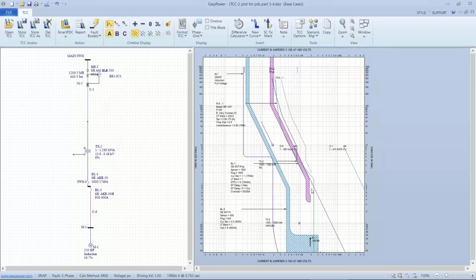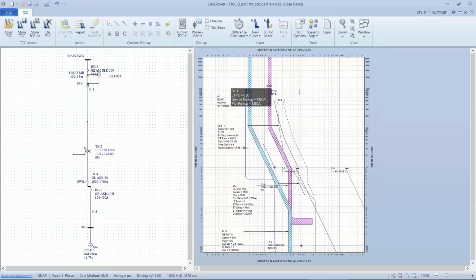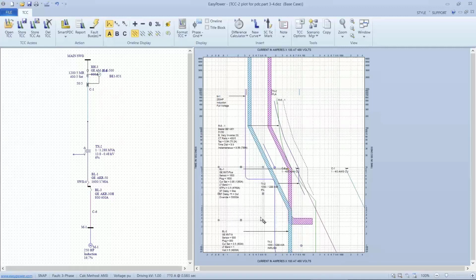Now, this breaker can be snugged up a little bit. What I'm doing is hovering over the curve and then adjusting it based upon its reference to the downstream device. In some cases the size of the label box gets in the way. So we're going to move the magenta breaker over a little bit.